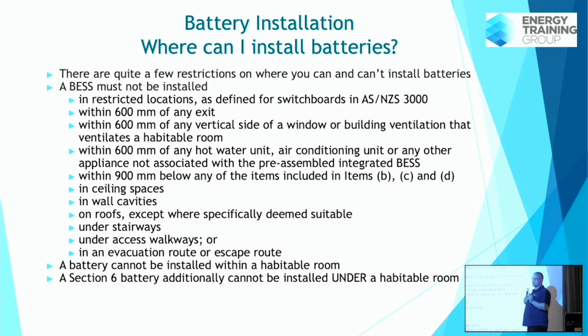Now, one thing to think about, what is associated equipment? The inverter is considered associated equipment, okay? So the inverter can be within the exclusion zone. The switchboard can also be within the exclusion zone, because it's associated equipment to the electrical installation. You can't install them in the ceiling space, in the wall cavities, you can't install them on the roof, you can't install them under a stairway, under an access walkway, or in an evacuation route. Okay, so you need to find a nice bit of clear wall to be installing batteries. Mostly you've got to be avoiding windows and doors. They're the main things you're considering when you're doing your site inspection.